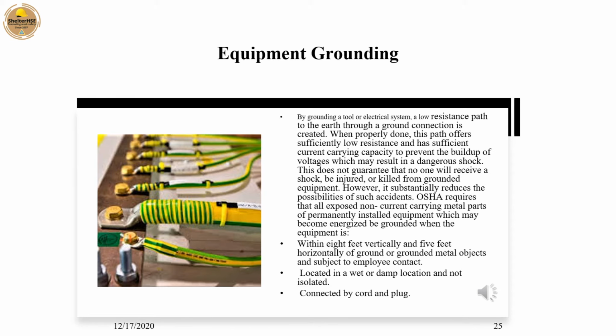OSHA requires that all exposed non-current carrying metal parts of permanently installed equipment which may become energized be grounded when the equipment is within 8 feet vertically and 5 feet horizontally of ground or grounded metal objects and subject to employee contact. Located in a wet or damp location and not isolated. Connected by cord and plug.